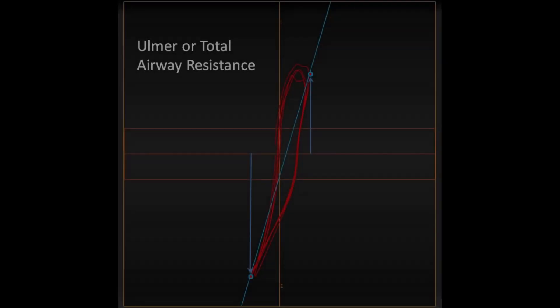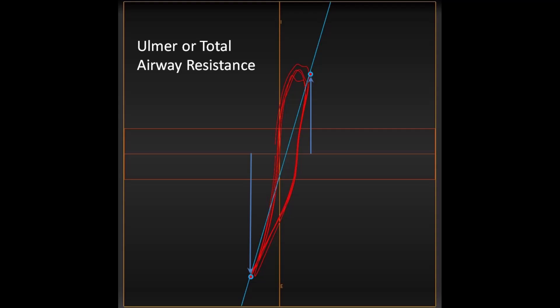One other method for adjusting the airway resistance loop may be seen outside of the United States. This method is called the Ulmer Method, or sometimes called Total Airway Resistance. The Ulmer Method defines the line of best fit between the points of maximal inspiratory and expiratory volume shift or pressure change. By adjusting the line of best fit to the maximal pressure change, you may have improved sensitivity at end expiration; however, you may also have increased variability.